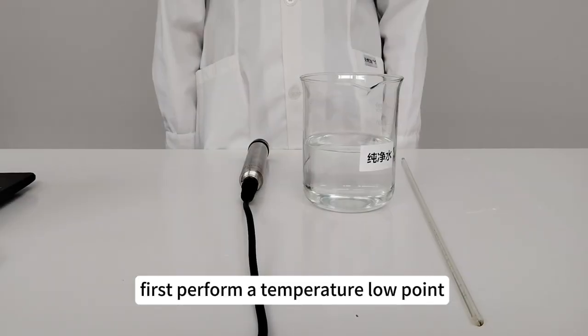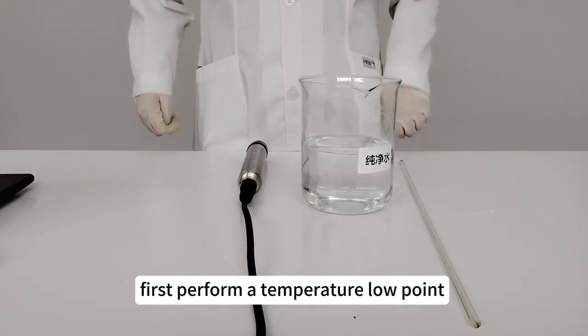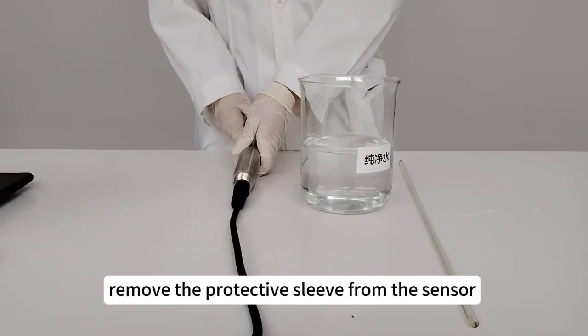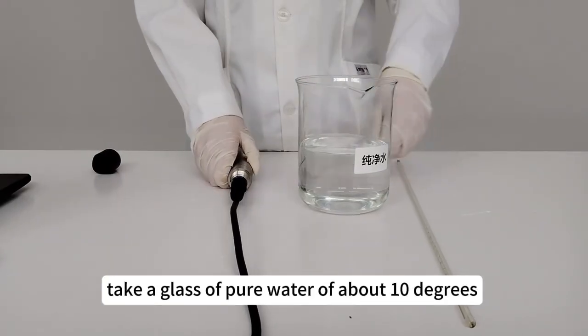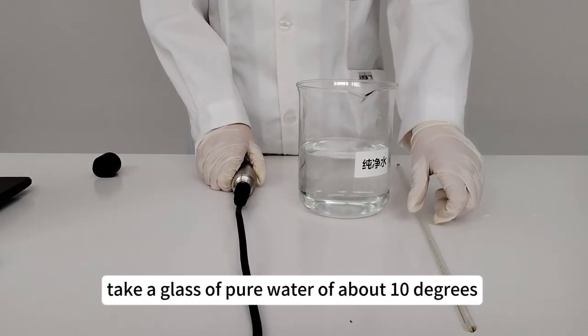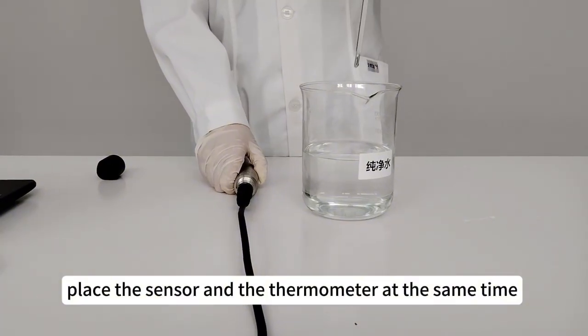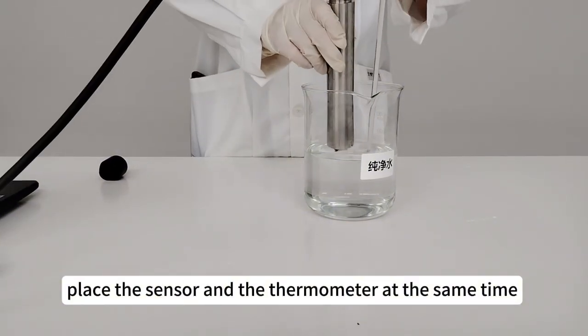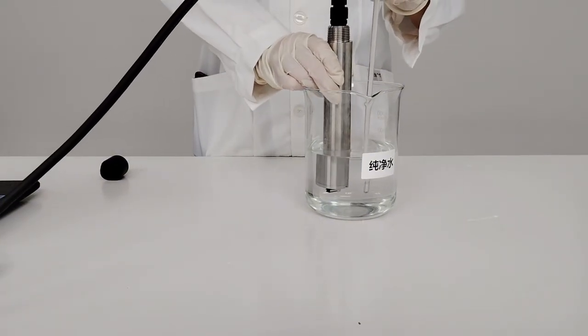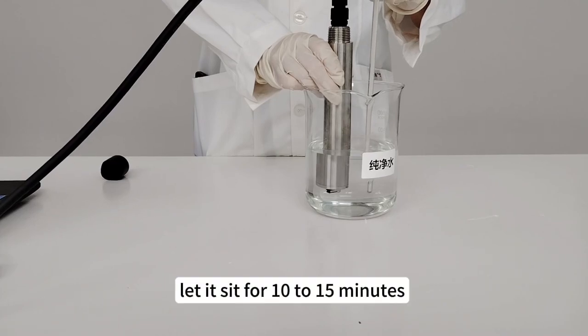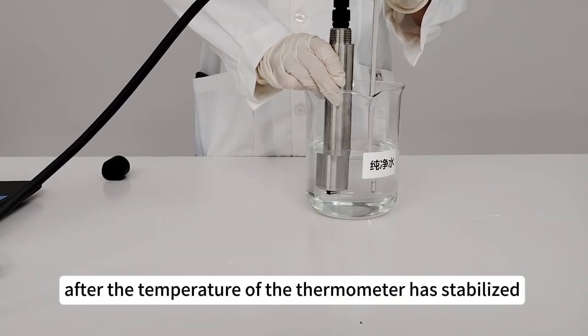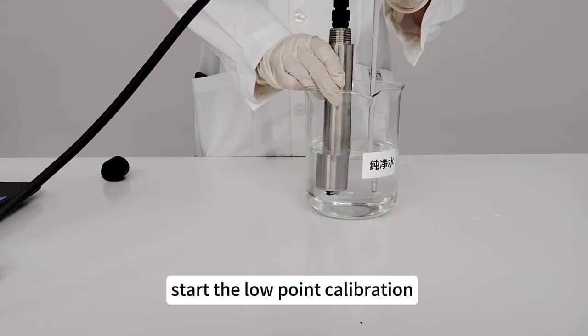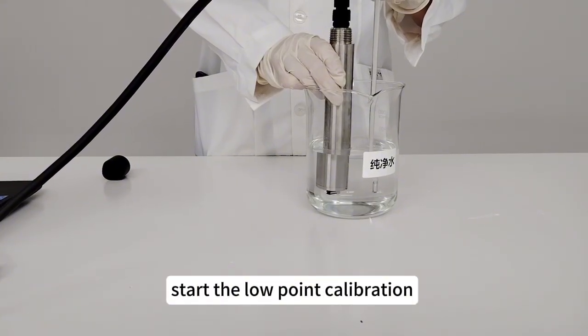First, perform a temperature low point calibration. Remove the protective sleeve from the sensor. Take a glass of pure water of about 10 degrees. Place the sensor and the thermometer at the same time. Let it sit for 10 to 15 minutes. After the temperature of the thermometer has stabilized, start the low point calibration.